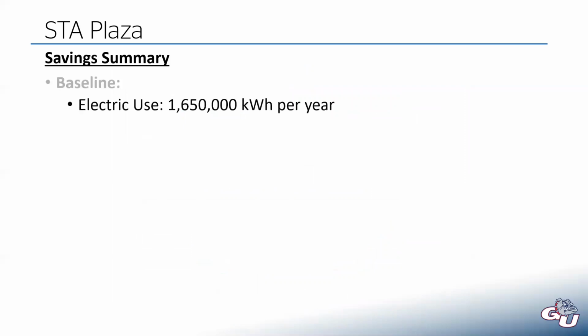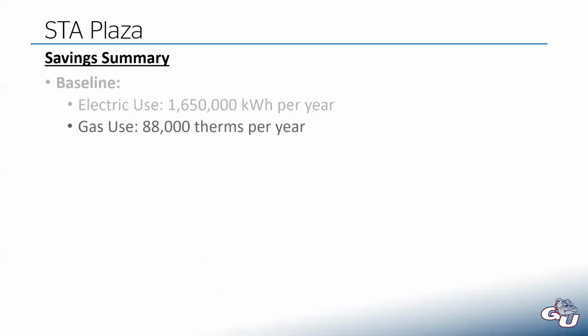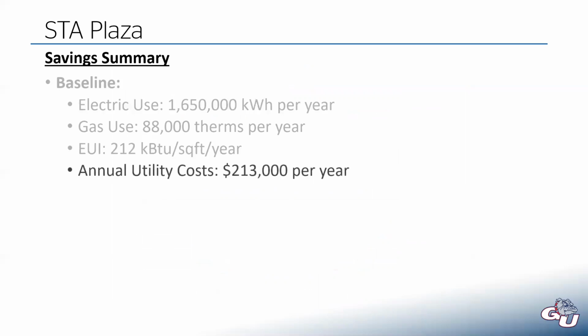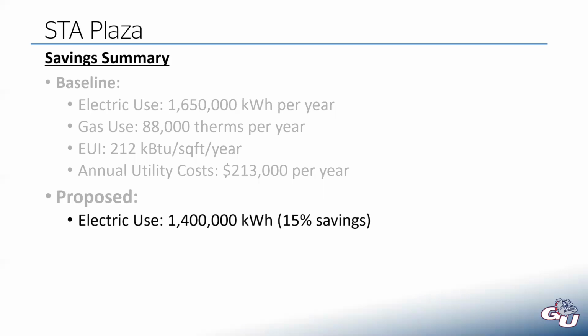So the summary, at the end of the day, how do we do? Our baseline data, they used about 1.6 million kilowatt hours per year, 88,000 therms per year. I mentioned an EUI of 212, which is extremely high. And they're spending a little over $200,000 per year on their utility bills. When we're done, we dropped their electric use to about 1.4 million kilowatt hours. So that's about 15% savings. That's not bad, but 15%, that's not going to make anyone's jaw hit the floor.